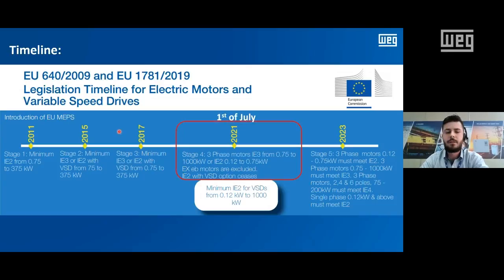But on the 1st of July 2021, the first day of this month, this new regulation, 1781, replaced the old one. It now has more demanding requirements for electric motors, but there are two new things here. In the past, you could use lower efficiency motors, IE2, with a variable speed drive instead of using an IE3 motor. But this is now no longer acceptable. So this option ceases. And the second point, the most important one, is that variable speed drives now also require some minimum efficiency levels. And in this case, the minimum efficiency level that you should now comply with is IE2.